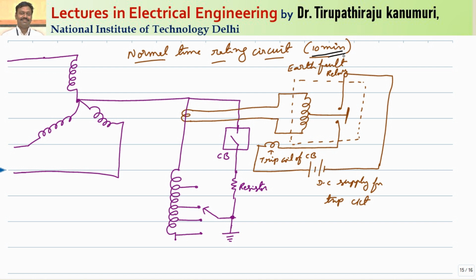So how will it be disconnected? As the fault current is very less, detecting it and isolating the circuit is a very cumbersome process, because even if some current is passing, that doesn't mean that current is because of the ground fault, because that can be because of unbalanced loading of the phases also. So that's why care should be taken for that.